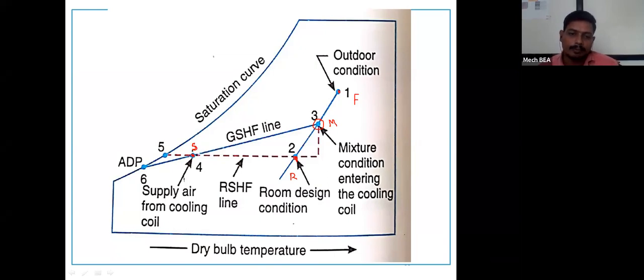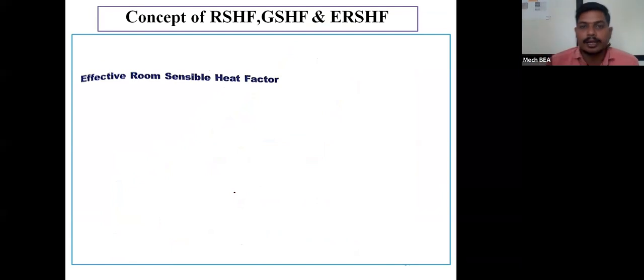The line joining point M and point S, that is the line joining the condition of mixed air and the condition of supply air, will be called the GSHF line. And one more line, the line joining point S and point R, the condition of supply air and the required room condition, will be called the RSHF line. So this line is the GSHF line and this line is the RSHF line. Now the third one is called the ERSHF. Up to this point we covered this topic in our last lecture. Now ERSHF line means effective room sensible heat factor line.